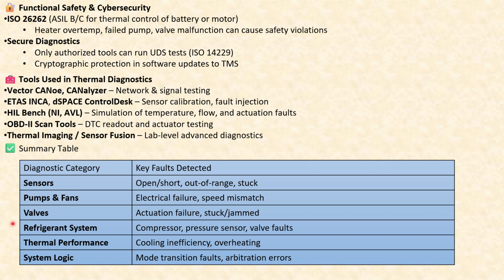Now, to finally summarize, these are all sensors, pumps and fans, valves, refrigeration system, thermal performance, and system logic. These are the various areas that fall under the diagnostic categories. Key faults like open, short, and out of range, electric failure, actuation failure, stuck or jammed, compressor and pressure sensor faults, cooling inefficiency, overheating, mode transition faults, and arbitration errors are all under the key faults detected.